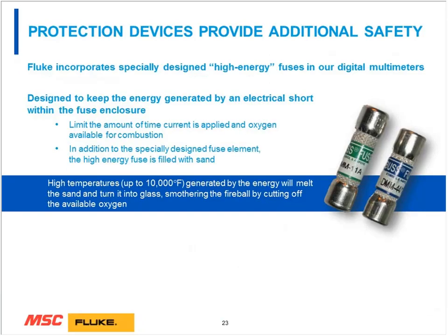Here's the fuses. A bit of recommendation, if you need to replace the fuse, whether it's a Fluke instrument or any instrument, always refer back to the manufacturer's recommendations on what fuse to use. Don't violate that. Very important that you use the correct fuse. As I mentioned, these are designed specially by Fluke, for Fluke, to have some sand inside, and it actually turns to glass, which extinguishes and smothers that arc that can be generated in the fuse if excessive current goes through.